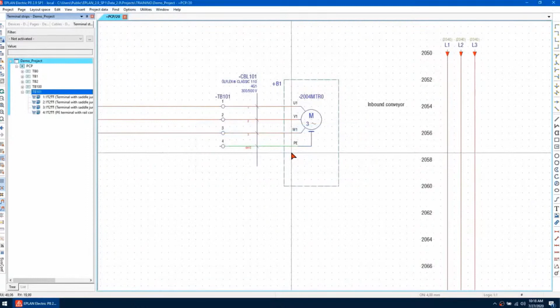To fix this, we go to parts management: utilities, parts, then management. I'll look for the part—this is the EBG16. If I go to properties and check this alignable box, click apply and then close, it will ask me to synchronize the parts database. I'll hit yes. Now when I go to edit the terminal strip and add the alignable accessory, I'll have this EBG16 here. I'll click OK, and as you can see, the accessory has now been aligned, and I can move the position up and down depending on where the accessory needs to be placed.